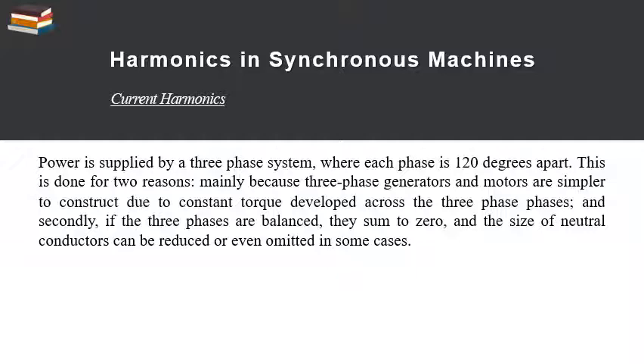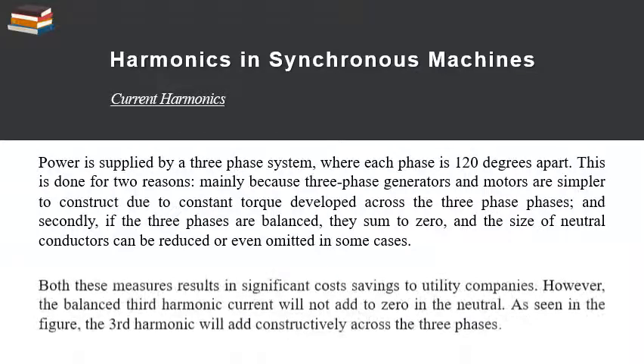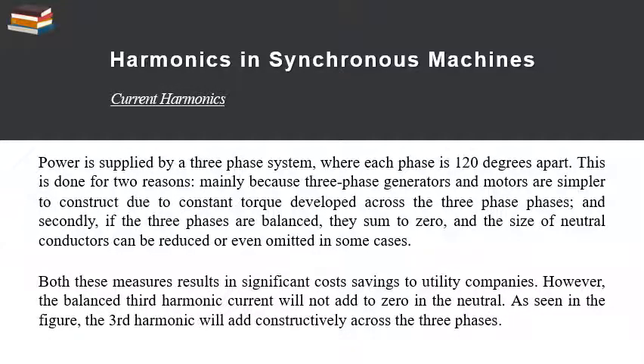This is done for 2 reasons. Number 1, mainly because 3-phase generators and motors are simpler to construct due to constant torque developed across the 3 phases. And secondly, if 3 phases are balanced, they sum to 0 and the size of neutral conductors can be reduced or even omitted in some cases. Both these measures result in significant cost saving to utility companies.